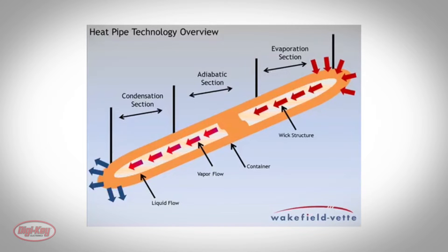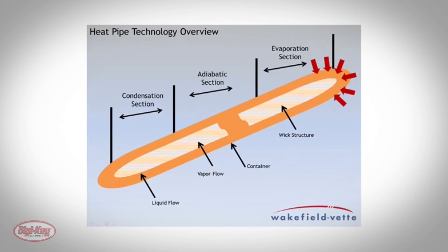As heat is applied to the heat pipe, the water will boil and turn to gas, which will move to the coldest section of the heat pipe, where it condenses back to a liquid. The performance of a heat pipe is a function of its length, diameter, wick structure, and overall shape.